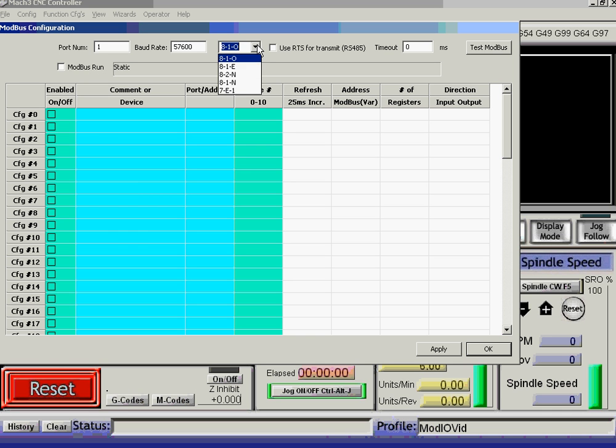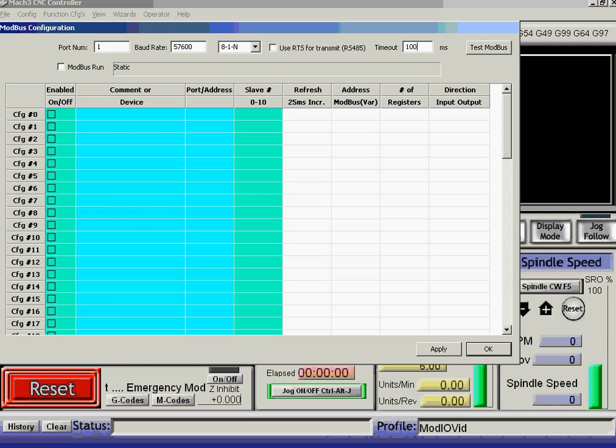I am plugged into COM port number 1 of my computer. It is configured at 57600 baud. It uses 8 bits, 1 stop bit, no parity. I'm going to say 100ms timeout for errors in the Modbus configuration.